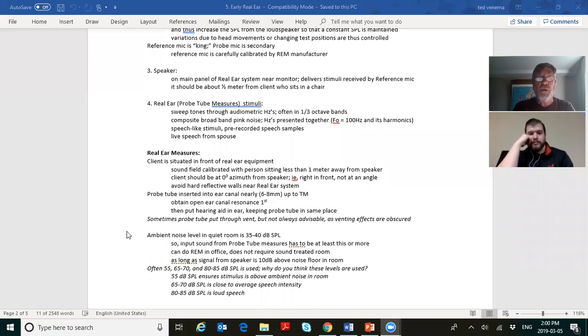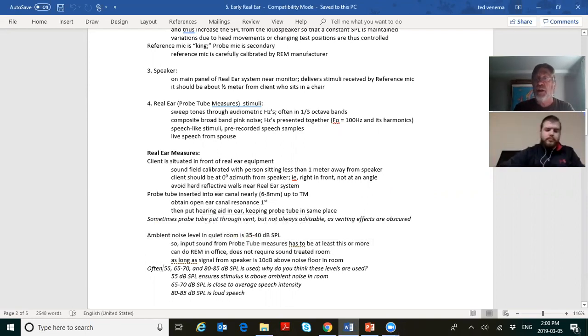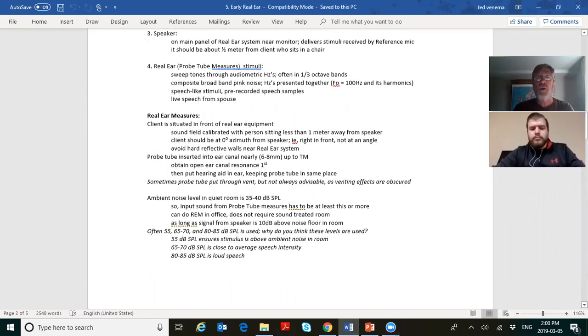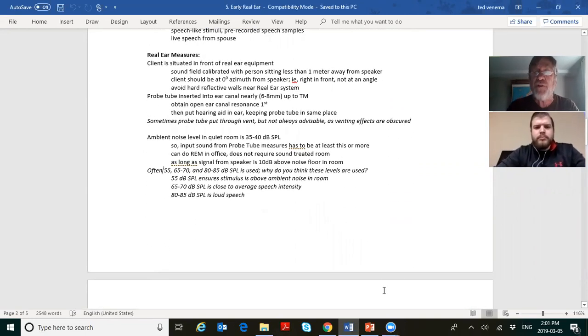Typical ambient room noise is about 35 to 40 dBSPL. So input sound from the probe mic system's got to be at least this or more. The levels used in real ear, and Gus Mueller told me yesterday, 55, 65, and 75 are actually the best ones to use. Not even 80. 50 you can, and 80 you can, but he suggests 55, 65, and 75.